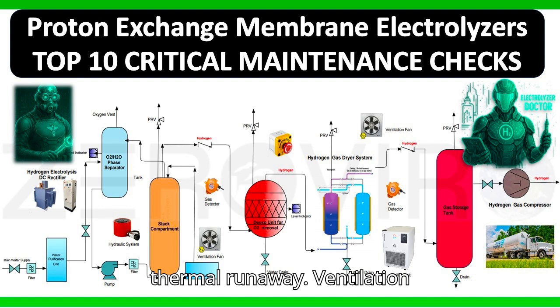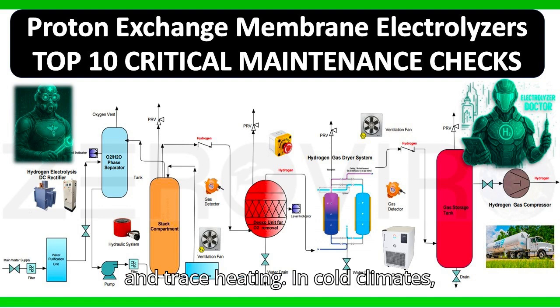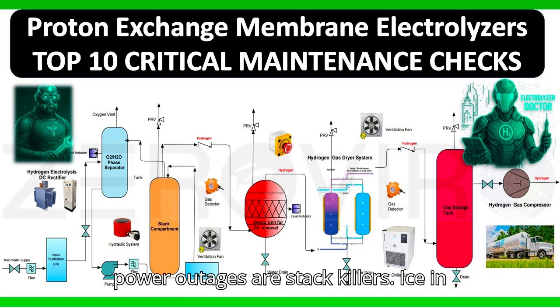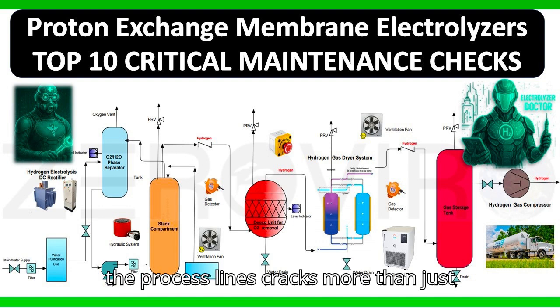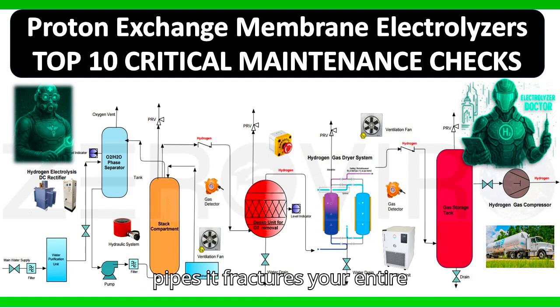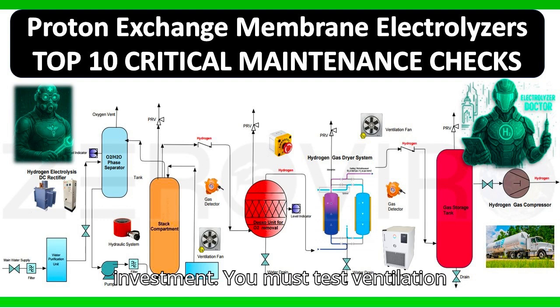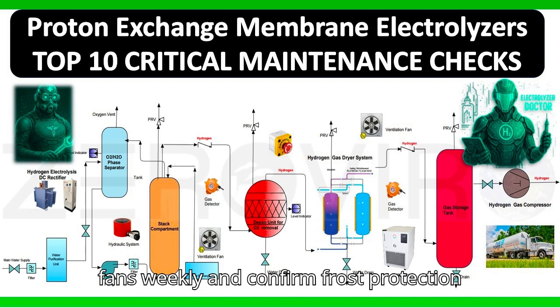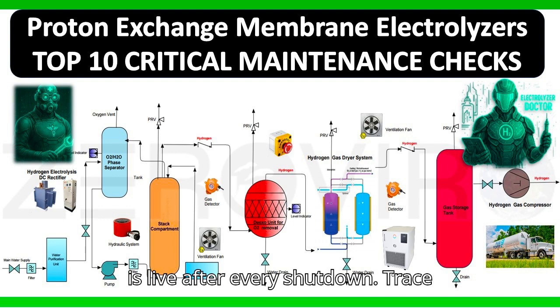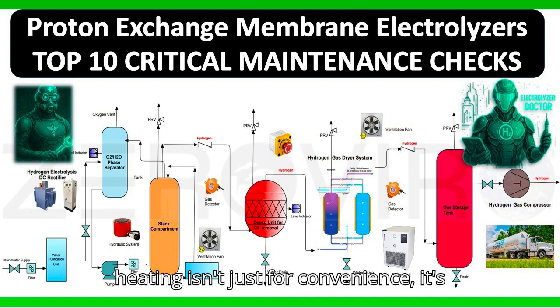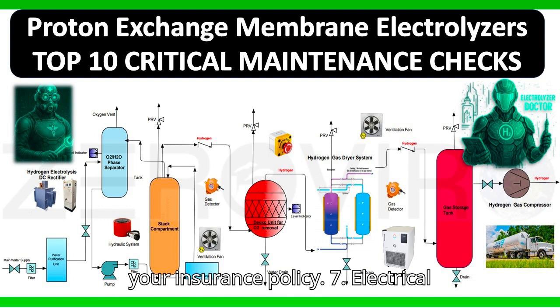6. Ventilation and trace heating. In cold climates, power outages are stack killers. Ice in the process lines cracks more than just pipes, it fractures your entire investment. You must test ventilation fans weekly and confirm frost protection is live after every shutdown. Trace heating isn't just for convenience, it's your insurance policy.